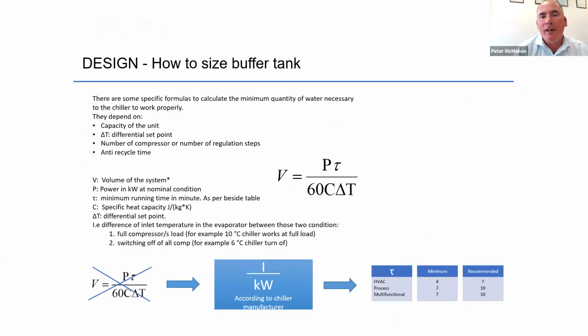Historically, we used to have to try and calculate the volume that was required based upon your capacity, the number of steps, number of compressors, your anti-cycle time, basically a number of factors we put into the equation. Thanks be to God, the manufacturers made it a lot easier for us now, and they simply tell us so many liters per kilowatt based upon the type of equipment they're delivering, because obviously they know what's built into that piece of kit. So where you may have had maybe 4 or 5 liters per kilowatt with a chiller or with a heat pump, if it's a process application, you typically double that to 7 or 8 liters. With a multifunctional heat pump, equally you double it. So you're talking pretty much 7, 8, even up to 10 liters per kilowatt, I should say.